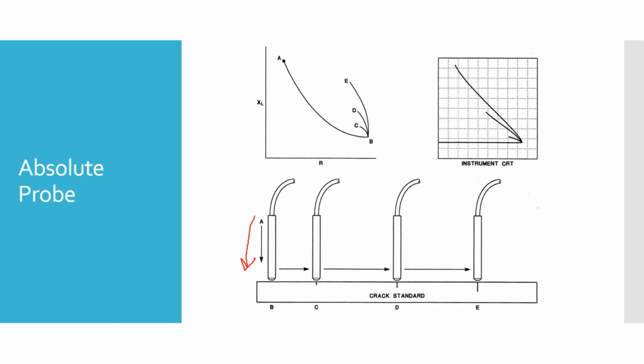As we bring the probe close to the part, going from A, the coil in air, to B, the coil sitting on the part, the indication moves from A to B on this graph, or on the display, coming straight from the left to the origin point B. Our origin point B is the standard: what the screen looks like when the coil is sitting still in a known good position.